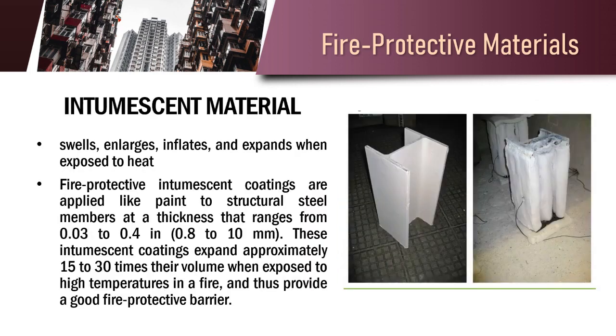The last example of fire protective materials is intumescent material. These materials swell, enlarge, inflate, and expand when exposed to heat. Fire protective intumescent coatings are applied like paint to structural steel members at a thickness that ranges from 0.03 to 0.4 inches, or 0.8 to 10 millimeters. These intumescent coatings expand approximately 15 to 30 times their volume when exposed to high temperatures in a fire, and thus provide a good fire protective barrier.